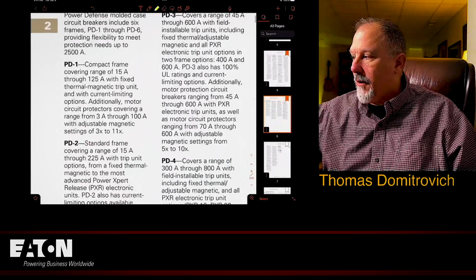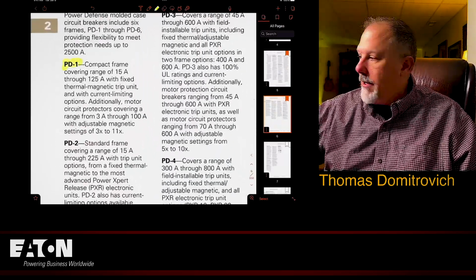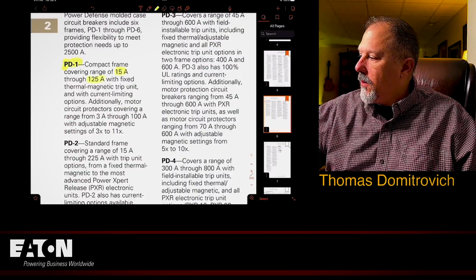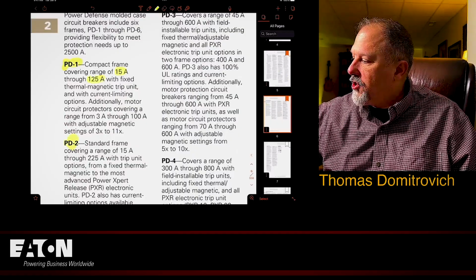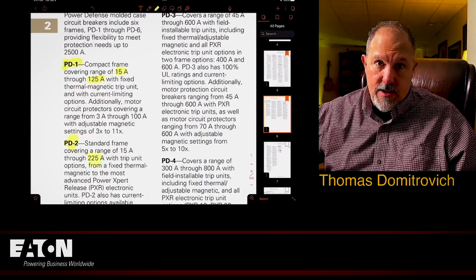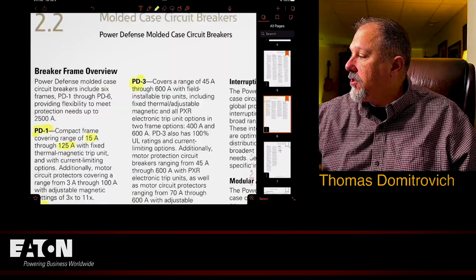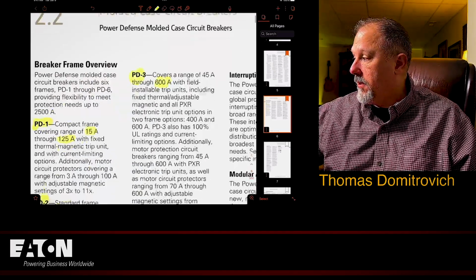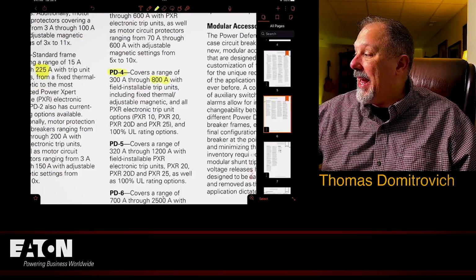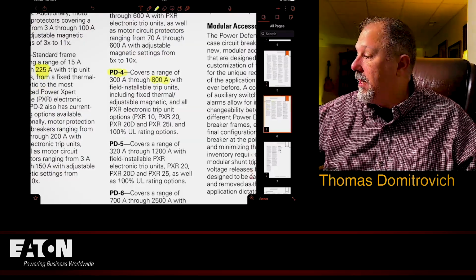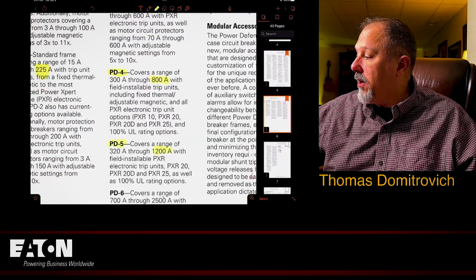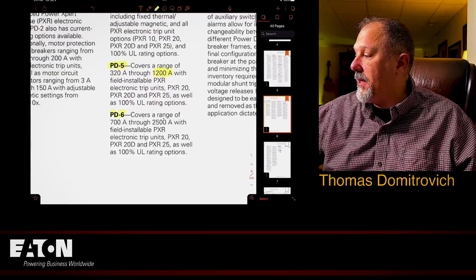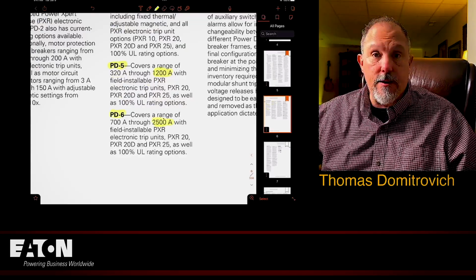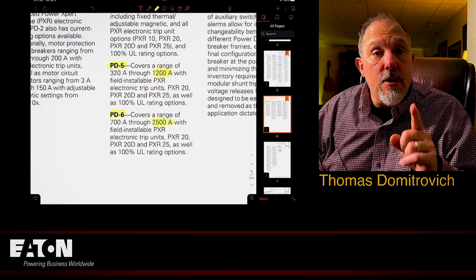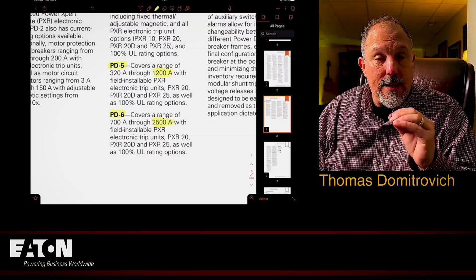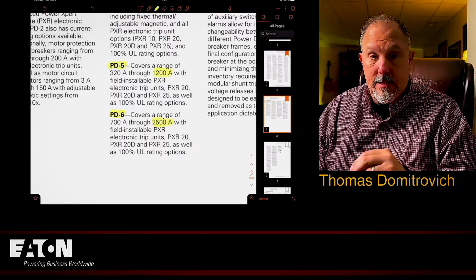Now here's your breaker frames. A PD1 will get you from 15 to 125 amps. PD2 goes up to 225 amps. PD3 goes up to 600 amps. A PD4 goes up to 800 amps. A PD5 goes to 1200, and then finally the PD6 goes up to 2500. So remember I told you, PXR20 is the one that gets you the arc flash reduction maintenance technology.